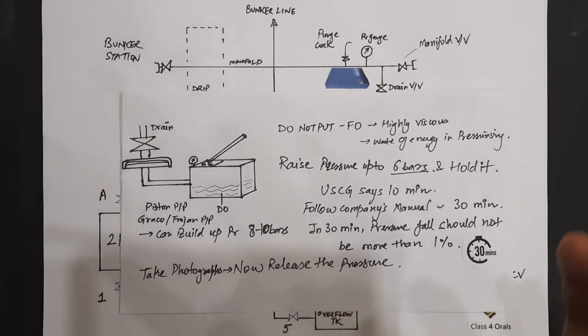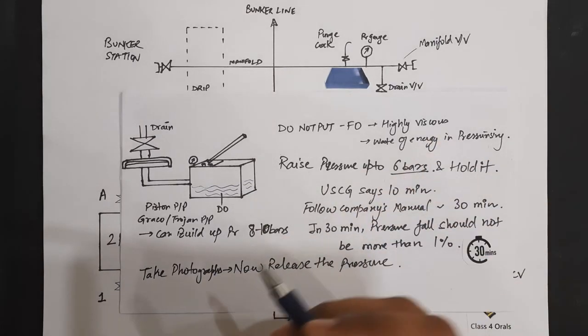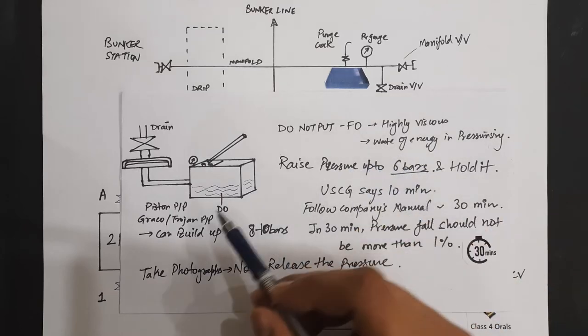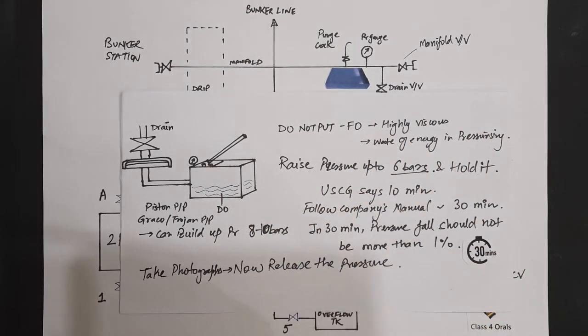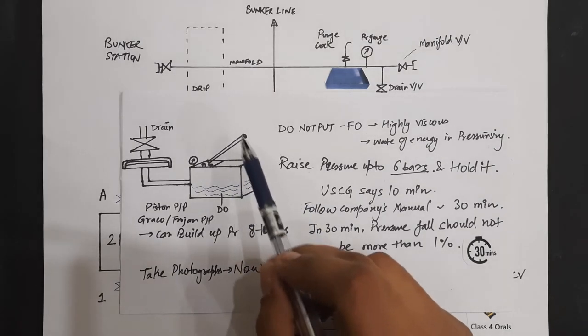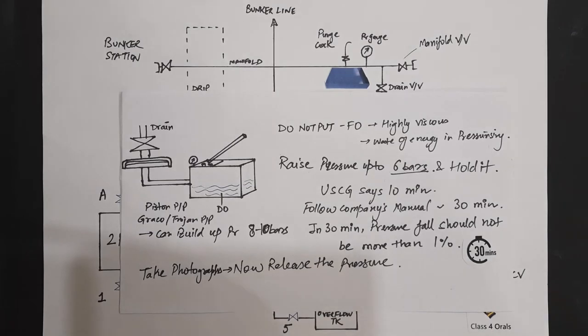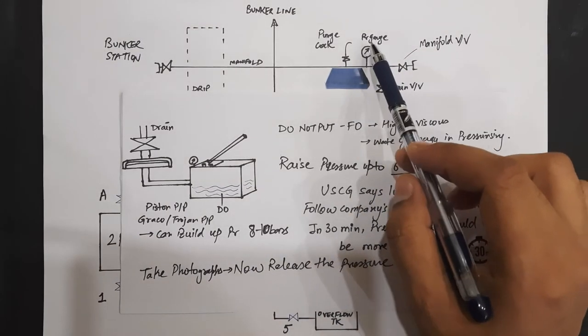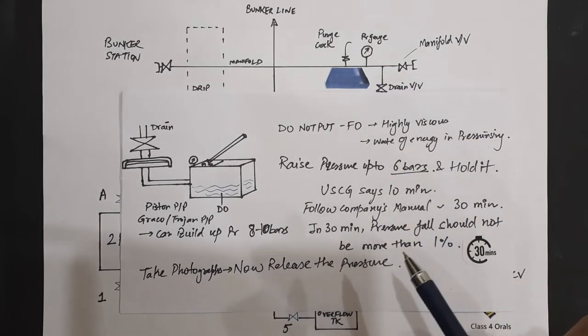Because if the tank is having 5 to 10 tons of fuel oil or bunker oil, and adding up the 3 to 4 liters or 10 liters of diesel oil is not going to make any difference in the bunker tank. So, we have to manually pump it and raise the pressure up to 6 bars. And then hold it. Once our pressure has reached on the bunker manifold 6 bars, hold it. Because we are going to test at 6 bars.